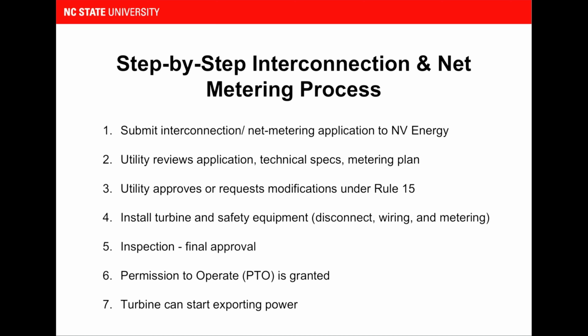Once approval is granted, the customer or installer can go ahead and install the turbine, along with all the required disconnects, wiring, and metering hardware. After installation, the project must pass a final inspection, usually by the local authority having jurisdiction, and then by NV Energy. If everything meets the standards, the utility issues permission to operate, also known as PTO, and after PTO is granted, the turbine can legally begin exporting power to the grid. This structured process helps ensure both safety and reliability for everyone.